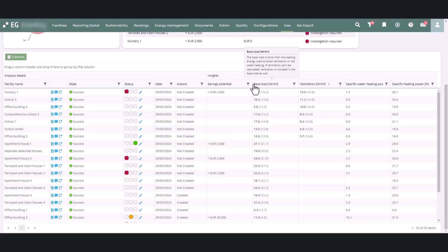The baseload column shows the heating base load of the building per square meter at an outdoor temperature of zero degrees Celsius. If the building has continuous ventilation around the clock, it is included in the baseload.